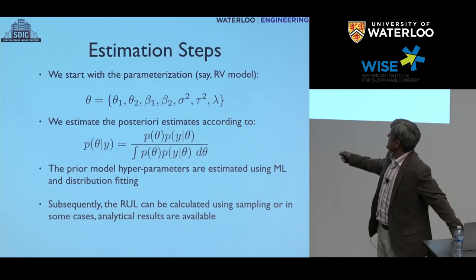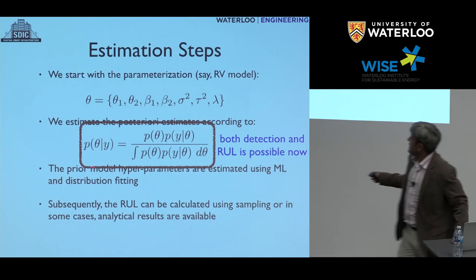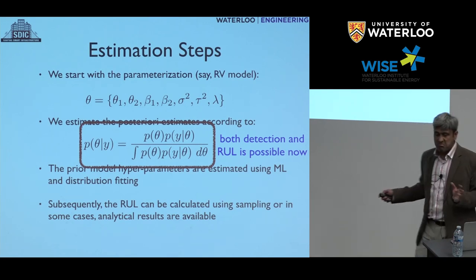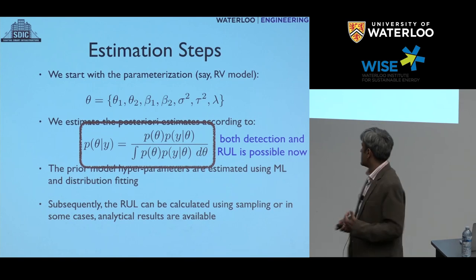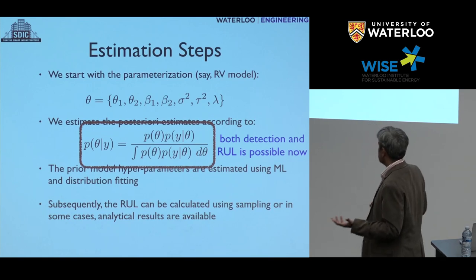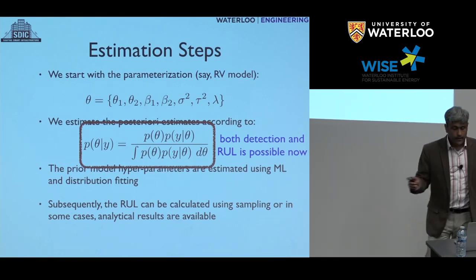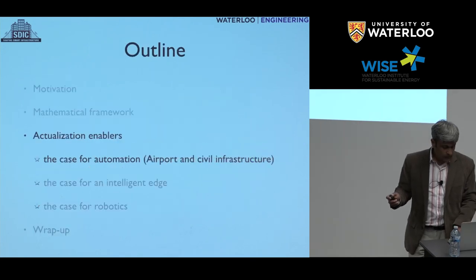This is common sense, but you can show it mathematically. When you're measuring very early on, all estimates are driven by the priors — the prior knowledge. As you go closer and closer to its end of life, they're driven more by the estimates you're actually getting from the data, meaning the data is better informing your estimates on remaining useful life than just your priors. The estimation steps are simple: parameterize the system, calculate posteriors using standard Bayesian methods, and estimate parameters using maximum likelihood or distribution fitting. Once you have the remaining useful life, your problem is essentially solved.